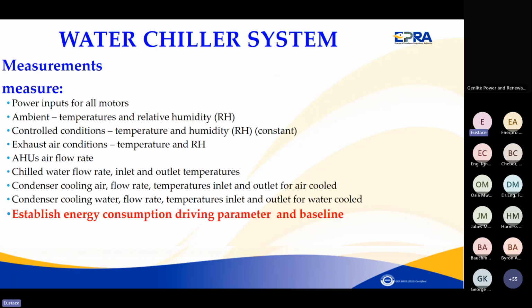So what do you measure? First, you measure the power inputs of all the motors. Please, if you have a pen and paper now, you can note this one. To measure the power input, please don't measure the instantaneous. Measure within the whole operation cycle. Like if it's a data center, there are two operation cycles. One is the day one. You measure the whole 24 hours.